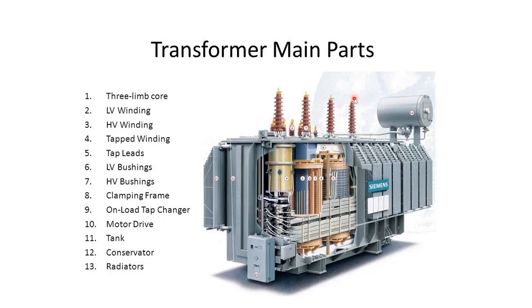because the insulation given here is lower. First, the electrical energy source is connected to either the low voltage or the high voltage terminal, depending on whether it is a step down or step up transformer, but the voltage level is linked with the insulation level, as you can see from these chocolate color insulator discs. These can be ceramic insulators or epoxy insulators, it can vary, but this particular thing that allows the current to go in or out of the transformer is called a bushing.